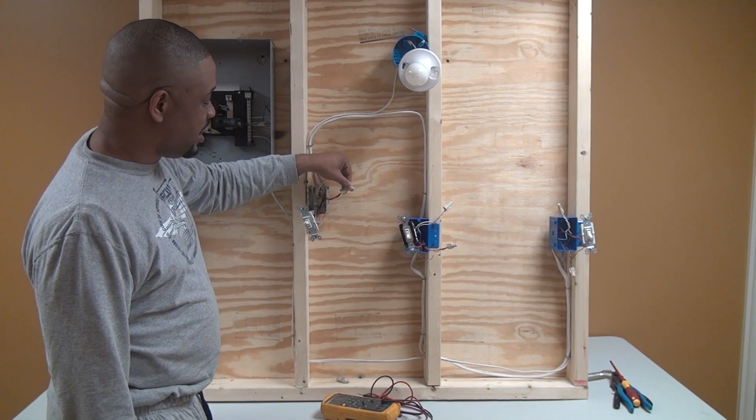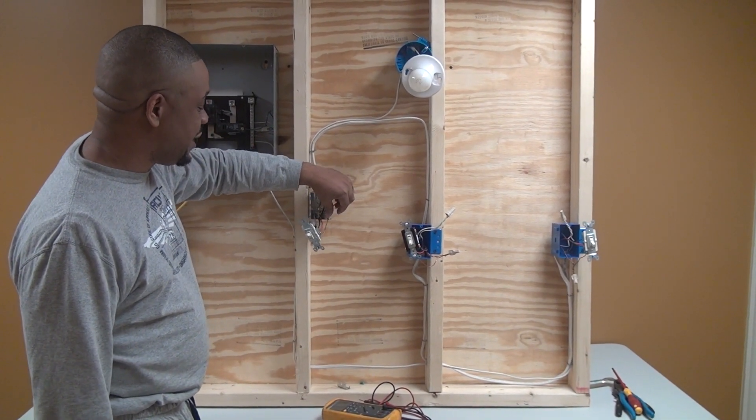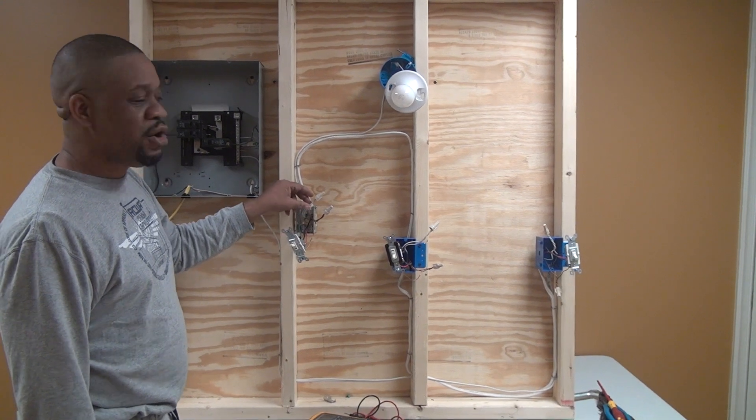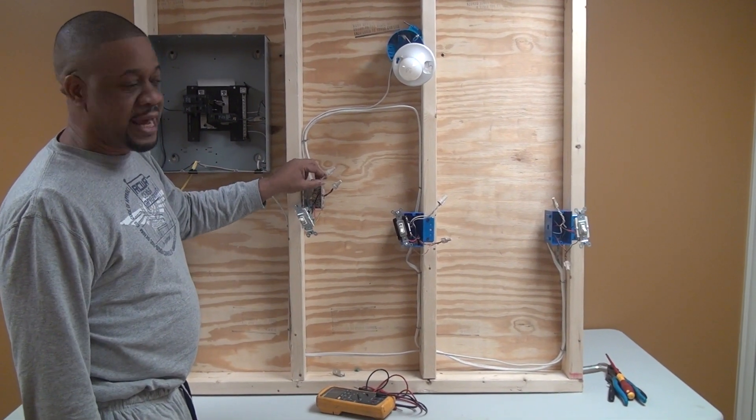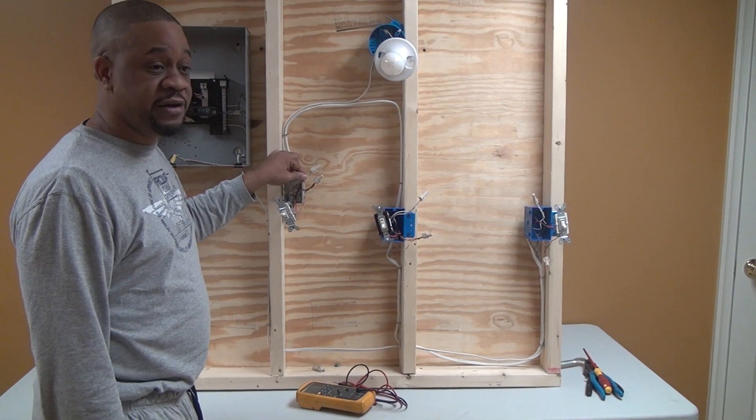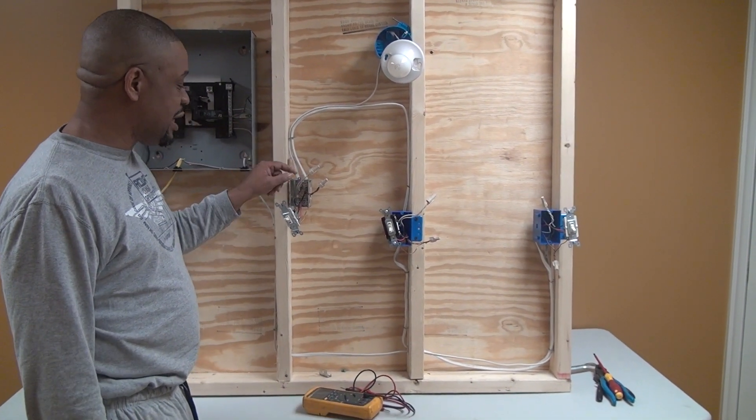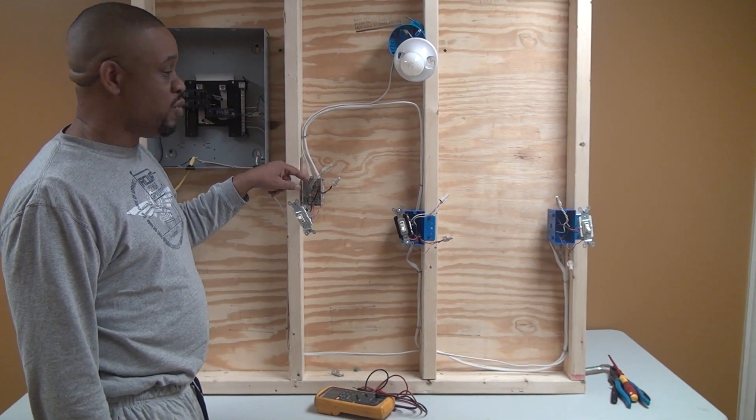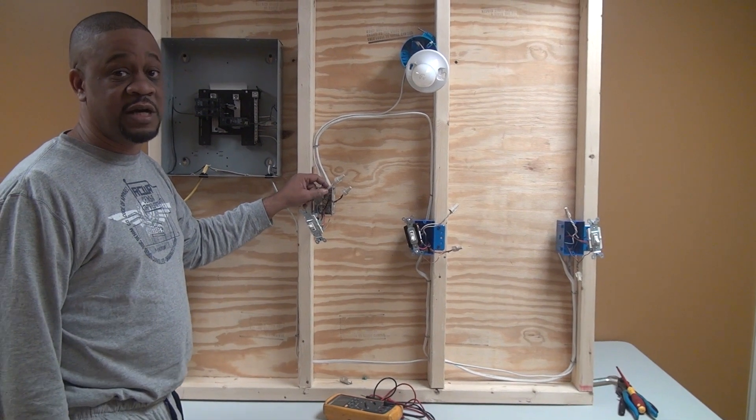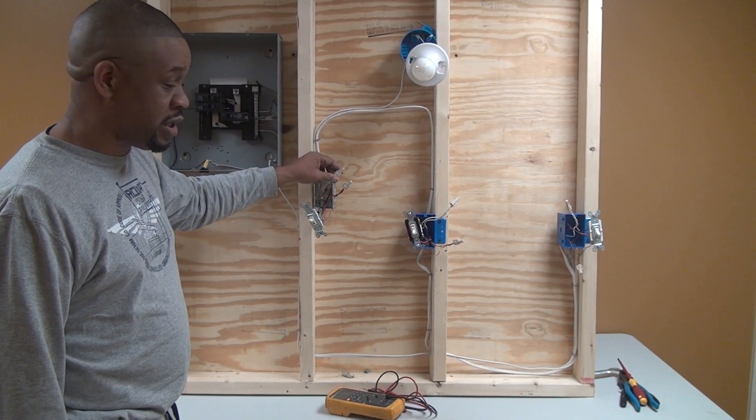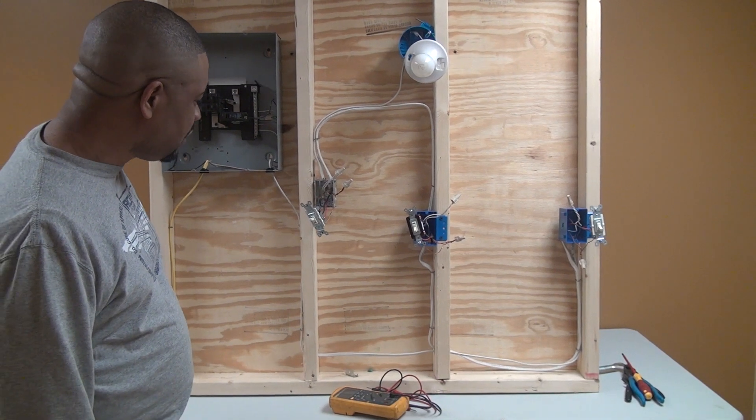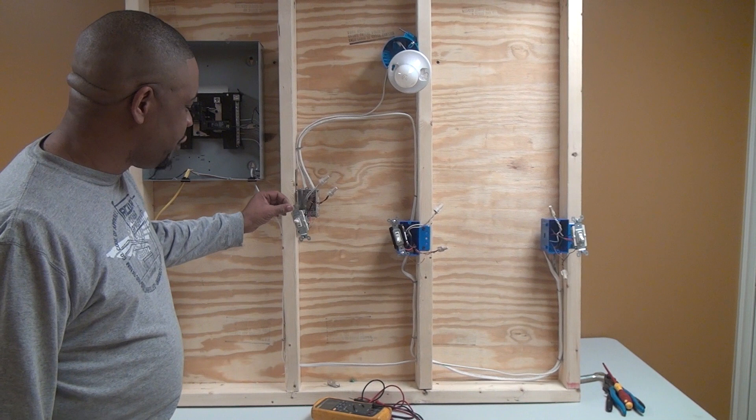What you didn't see on the screencast was the grounding conductor, this bare copper wire. That's your ground wire, or your grounding conductor. It can be confused with the grounded conductor, which is the white wire, or neutral. Like I told you guys, it actually acts as a return path for your electricity, in which case, that means that this wire actually carries current. So, it's a very dangerous wire. Even though it's grounded, if you were to open it up, you have actual current on one side. The side that's not going back and being bonded to wherever your grounding source is. So, be very careful that the white wire is a current-carrying conductor, the grounded conductor, the neutral, which means that it carries current, and it can hurt you.